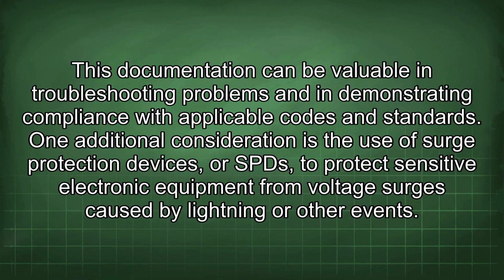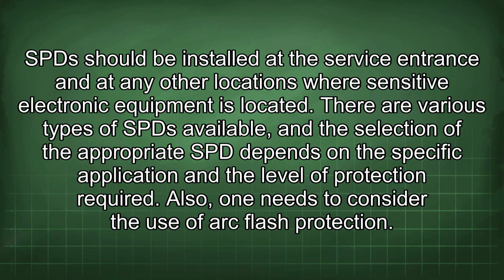One additional consideration is the use of surge protection devices, or SPDs, to protect sensitive electronic equipment from voltage surges caused by lightning or other events. SPDs should be installed at the service entrance and at any other locations where sensitive electronic equipment is located. There are various types of SPD available, and the selection of the appropriate SPD depends on the specific application and the level of protection required.